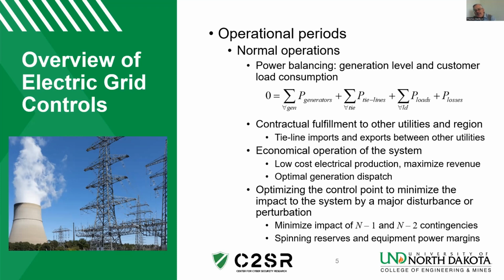So the objective there is you don't want to run a system so economically that if an event took place, you would not have the right additional resources to keep the system in operation. So embedded in this are the spinning reserves and power margins that are necessary to keep the system operating with the loss of one or two major pieces of equipment.